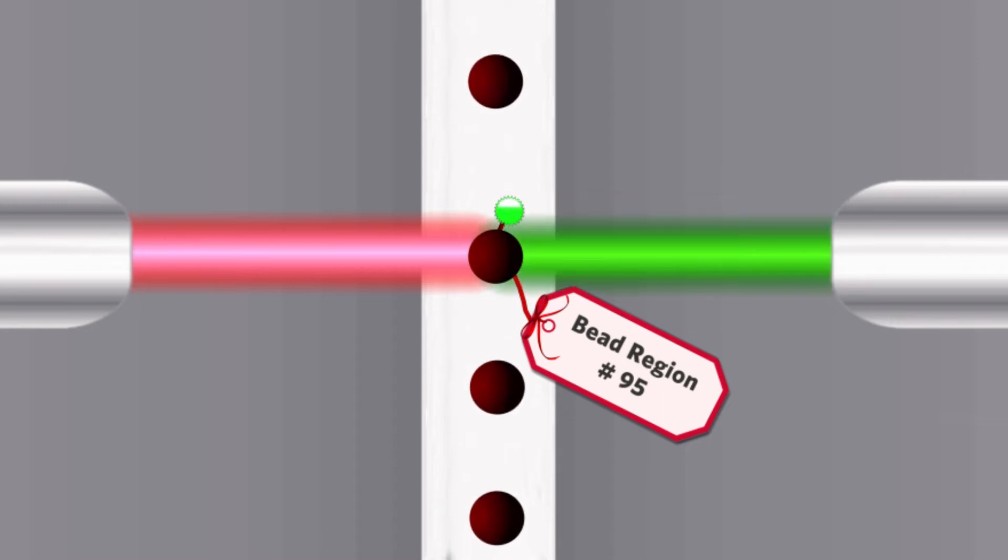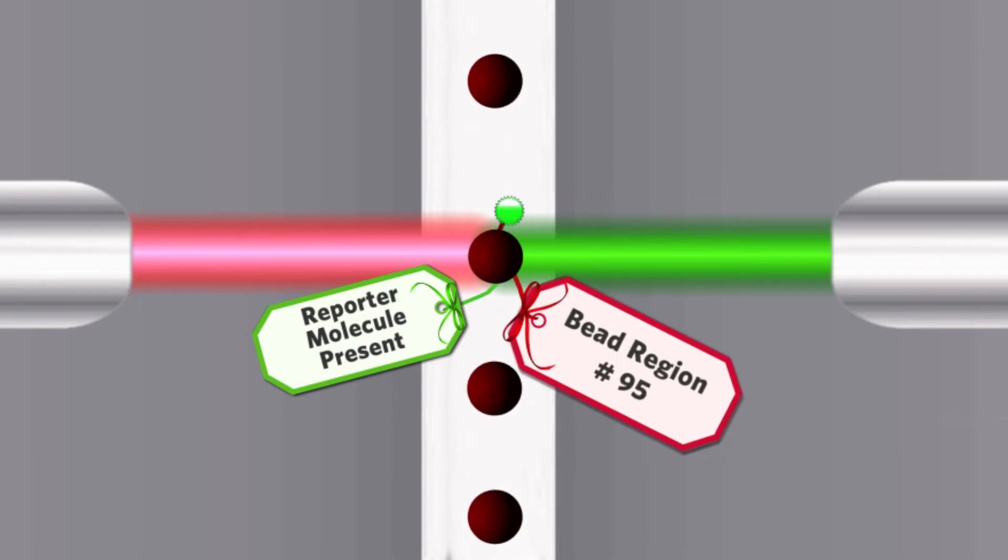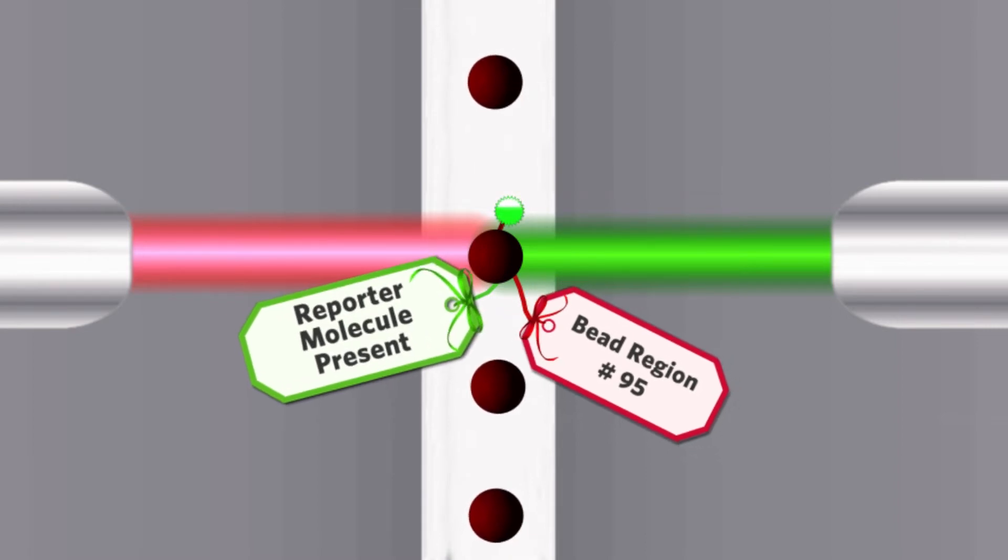The green 535 nm laser identifies the fluorescence of the reporter molecule. It works with its own sensor. Both the bead ID is mapped and the median fluorescence intensity is measured.